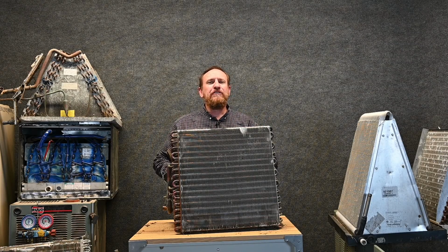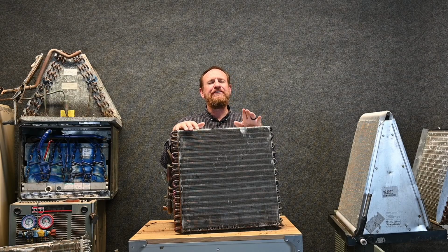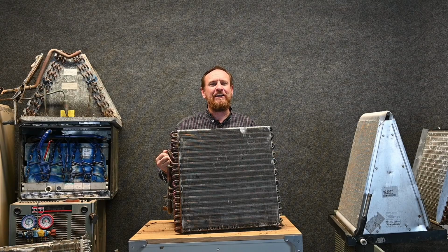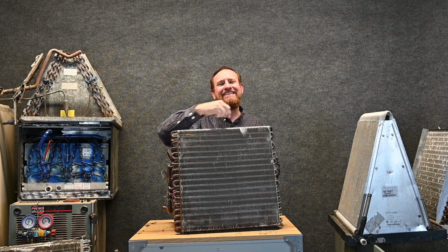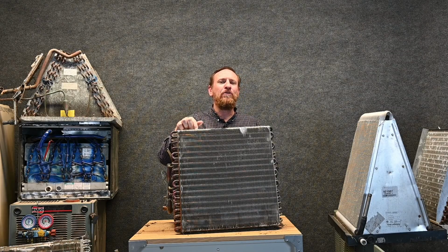The old refrigerant used an alkylbenzene or a mineral oil, and that oil did have an issue with moisture turning to acid eventually. But now we use polyester oil, which is very susceptible to moisture, and if we don't pull a good deep vacuum, that oil actually starts turning to an acid. That acid starts eating away on the evaporator coil from the inside out. So we start pitting and making holes in the evaporator coil on the inside.